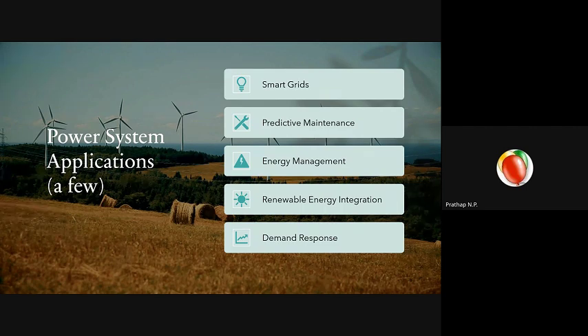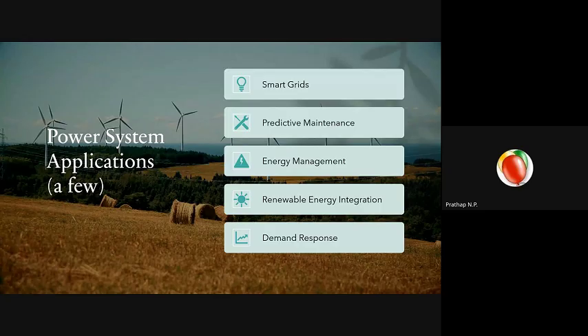What this facility did was they started incorporating these high sampling IEDs in their meters, and they started to record their demand on a continuous basis, not just a theoretical calculation, but actually measuring on a continuous basis. So after 8 months, they found that their demand was way less than what was theoretically calculated. So they submitted another application to the utility and said that, based on these values, we have a lesser demand, so we want to reduce the electricity bill. And you won't believe it, they reduced their bill by $2 million per year, just by trending these demand values. That's happening because of these devices that can communicate over the network, and you can trend them and store the data.